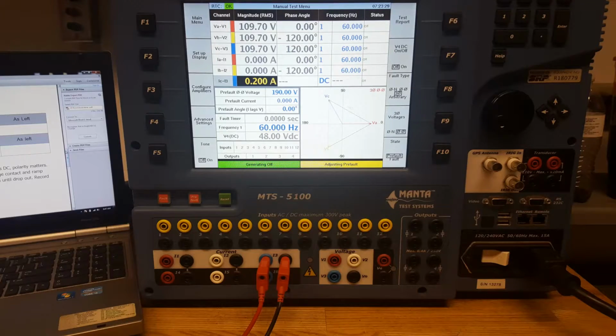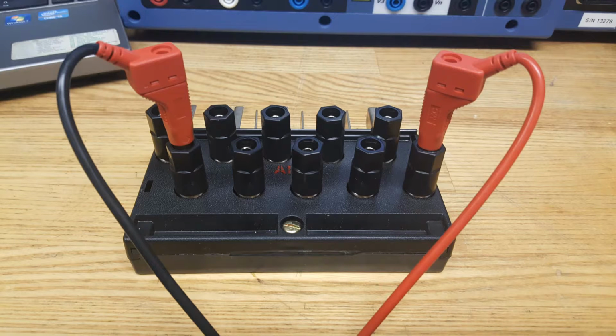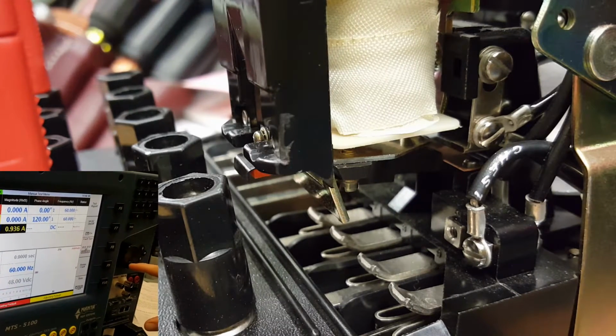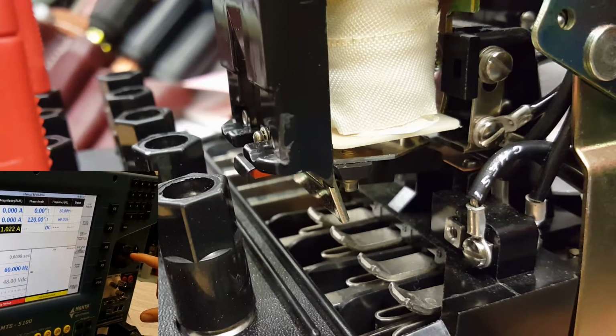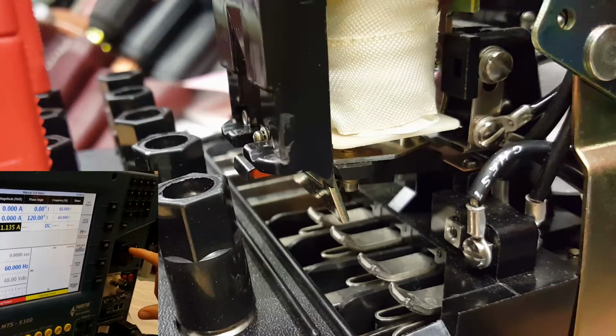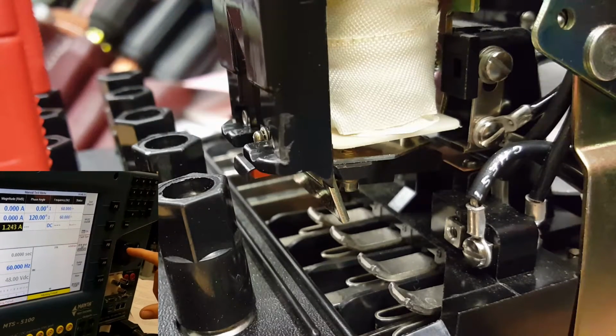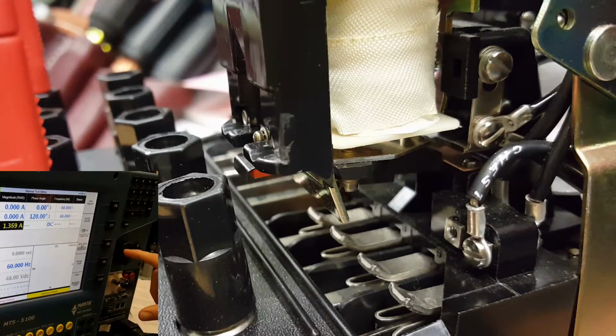For the target test and seal-in, we're going to be pushing DC in 10 out 2 according to whatever your tap value is set at. Our nominal value is going to be whatever the tap is set at. We're looking at a range of minus 50% to positive 120%. So just as long as the ICS operates within that range, it's going to pass.